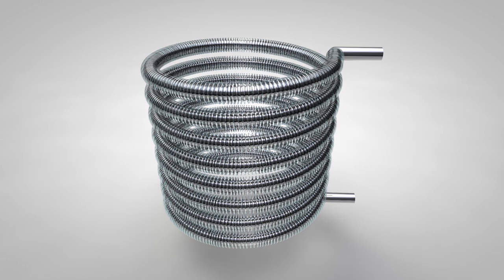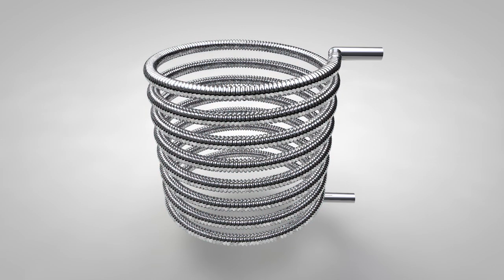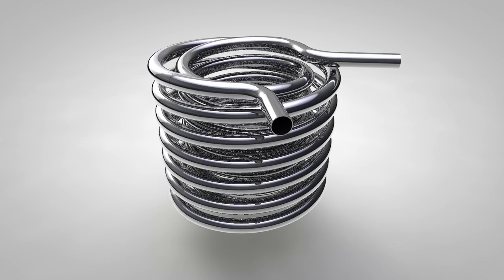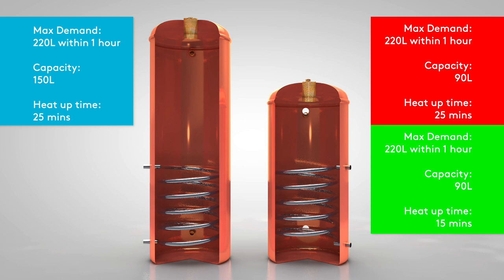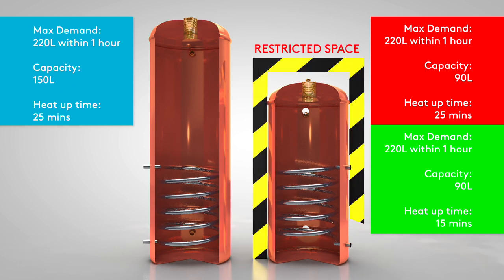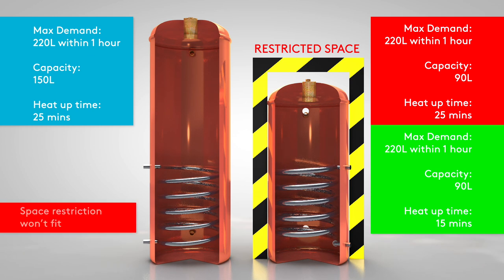High kW ratings are also essential for thermal stores and are most often used in copper cylinders to compensate for when an undersized cylinder is used due to insufficient space, to help achieve the required volume of hot water with a faster heat-up time.